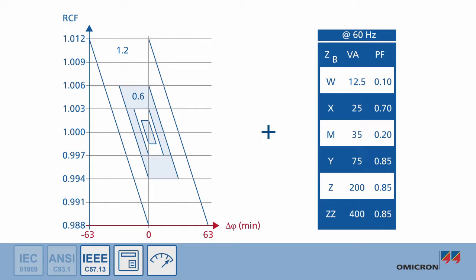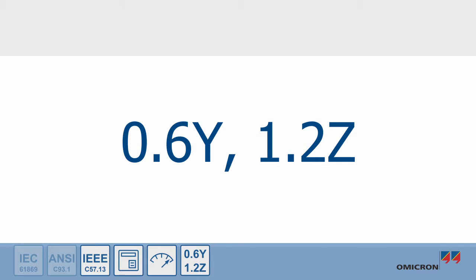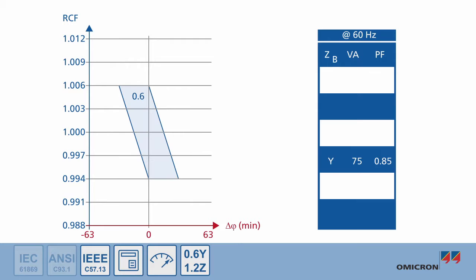Consequently, a combined accuracy burden rating is given. For instance, 0.6Y1.2Z means 0.6 accuracy class for burdens up to 75VA and 1.2 accuracy class for burdens from 75 to 200VA.